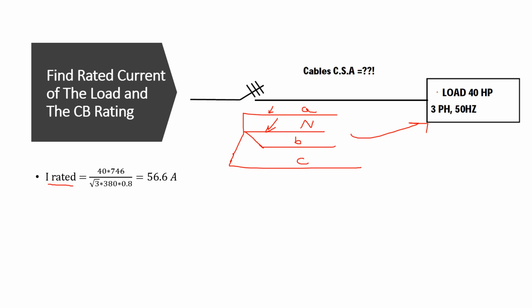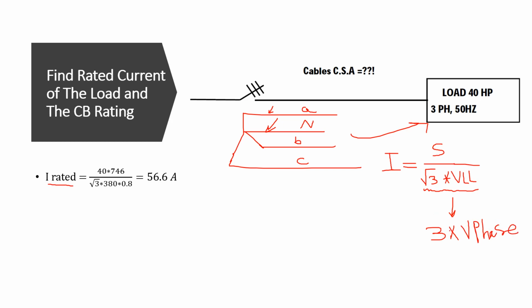In order to find the rated current of any load, remember that the current is equal to S, the apparent power, divided by root 3 multiplied by V line to line, the line to line voltage. Instead of root 3 V line to line, it can be 3 multiplied by the phase voltage, V phase.